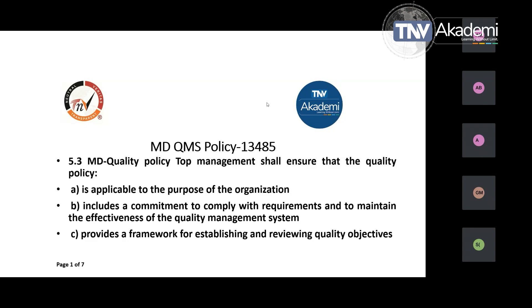So if we can understand it very clearly that we are talking of quality management based upon to implement the medical devices. The top management needs to ensure that yes policy is available and it is applicable to the purpose of organization. In some organizations we have seen they have said policy but they have forgot to include the medical devices which they are manufacturing or trading or servicing or the lab ingredients, the chemicals, the sanitizers and all they all fall into the medical devices category. So they should talk of that into their policy.